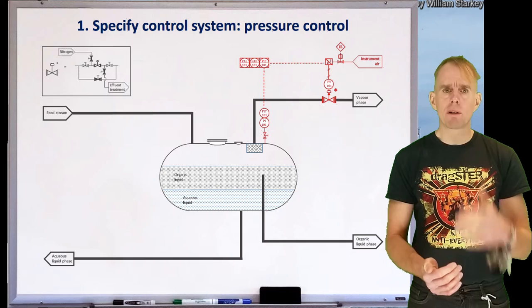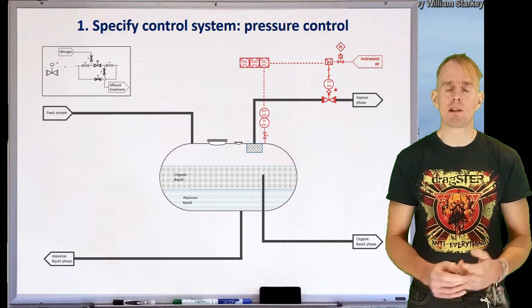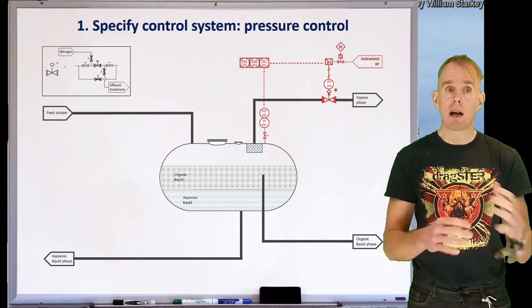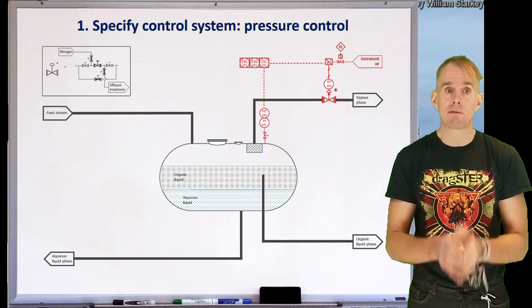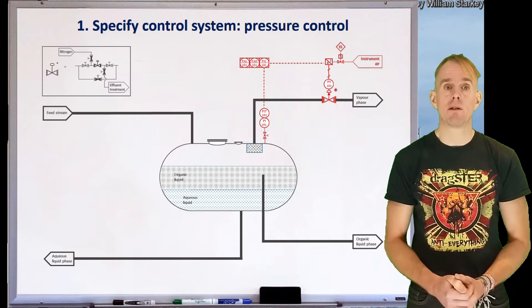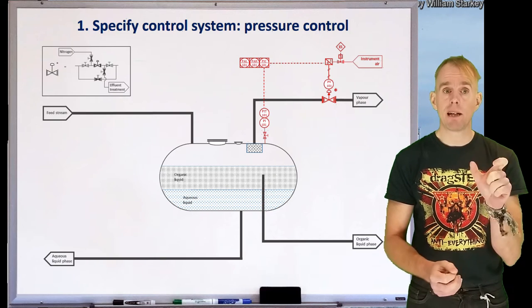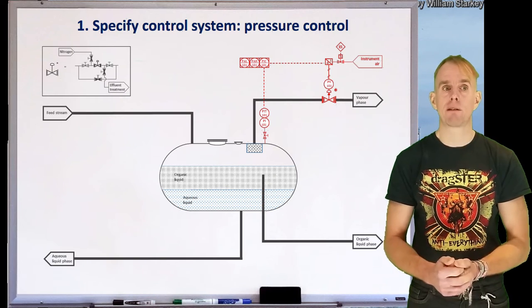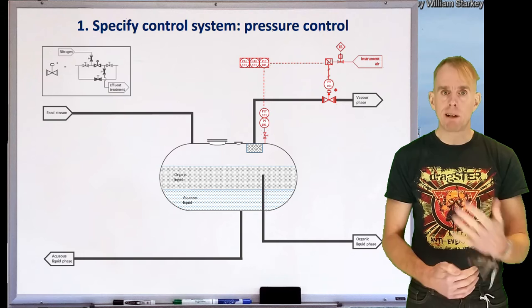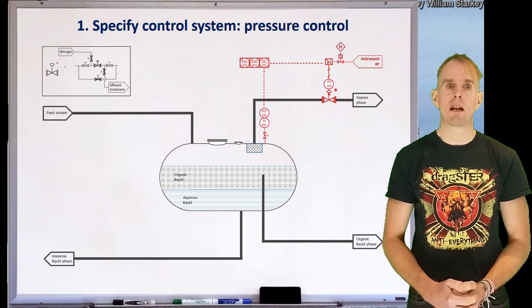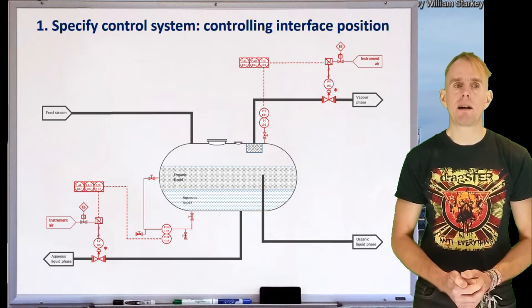So there's our pressure control system: a pressure sensing element, a means of converting the measurement into a standard 4 to 20 milliamp signal, alarms and a controller, a current-to-pressure converter for the pneumatic valve, and a connection to the emergency shutdown system. Note that the control valve assembly is marked with a shortcut asterisk, indicating that the control valve has its own isolation valves, a bypass leg, a vent and a drain as discussed in the last part of this lecture. That's the steady state control.